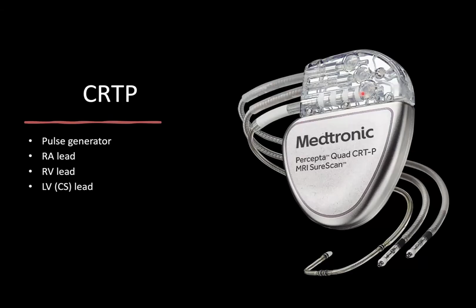I just want to point out that the header for an IS4 lead, IS4 means a quadrupolar, looks like this. It looks not very dissimilar to the header for a DF4, which we'll discuss later. And then you've got the two bipolar lead placement positions for the device.